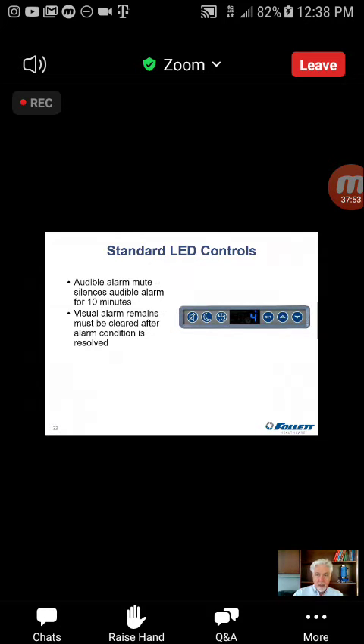The reason that we do that is, suppose this unit is placed in an off-site clinic, maybe that's not manned 24 hours a day. Suppose there's a power outage during the night and we don't have backup generators at that location. So what's going to happen? The unit shuts down, the temperature is going to go up, okay? If power is restored before the staff returns in the morning, the unit's going to fire up, and so the audible alarm will be stopping, okay? However, the staff won't know there's anything wrong unless we keep that visual alarm there. That's why that stays. So when they come in the morning, they see that, they know something bad happened during the night, and then we can do some investigation.